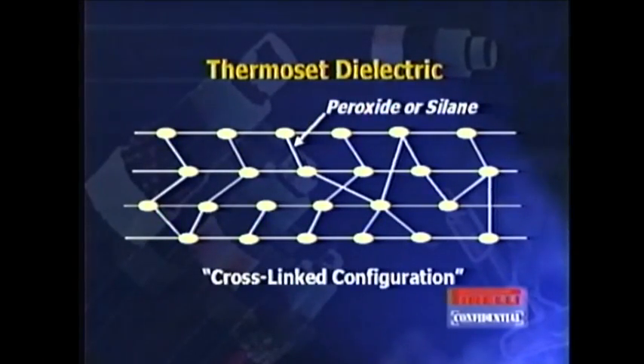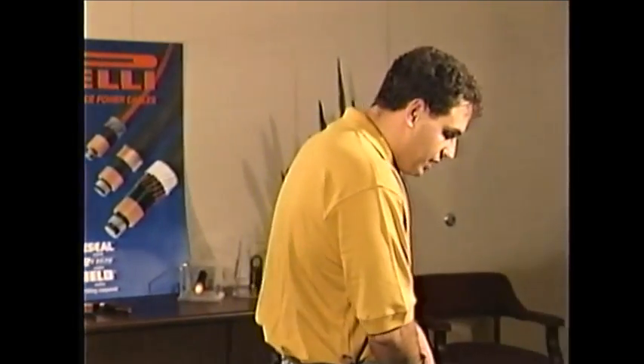In order to change a material from a thermoplastic state to a thermoset state, you have to introduce some cross-linking agent. There are various types of materials that you can use for that. One of the most common is peroxide, which is used very commonly in medium voltage cables. Peroxide is introduced, and you cure it under high heat and high pressure. And you have a cross-linking process, which in turn will give you a material that cannot be melted. Another way to cross-link a material is to introduce a compound called silane into the process, and you cure this using moisture. This is used commonly in low voltage materials and achieves the same effect.